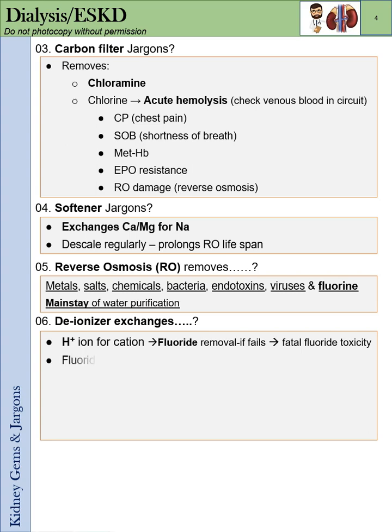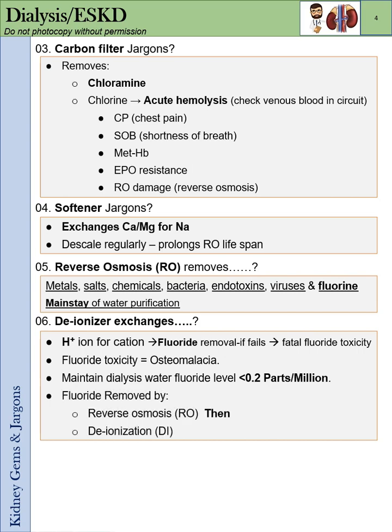The deionizer exchanges hydrogen ions for cations, causing fluoride removal. If it fails, it causes fatal fluoride toxicity. Fluoride toxicity causes osteomalacia. You have to maintain the water fluoride level at less than 0.2 parts per million. Fluoride is removed first by RO, then by deionization.